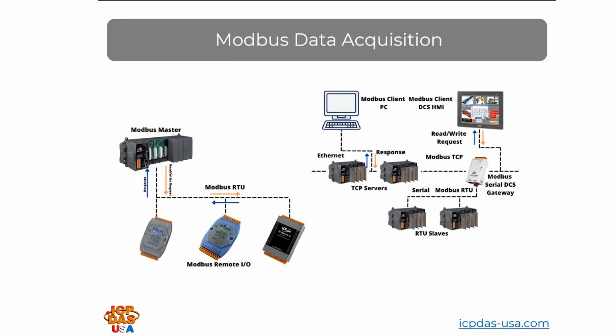On the left, you can see a Modbus master broadcasts messages to the data acquisition devices. The broadcasted messages contain a unique address identifier for the intended recipient. Only the intended recipient with the unique address will reply with the requested information. Data is stored in memory registers, usually indicated with a Modbus register mapping table.